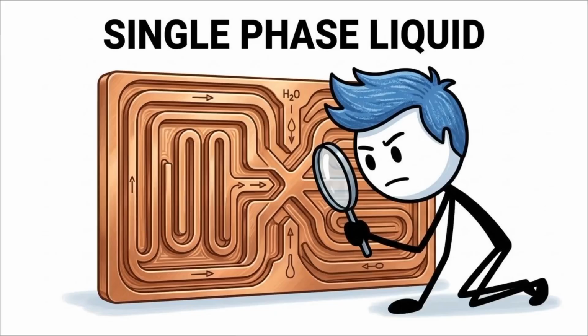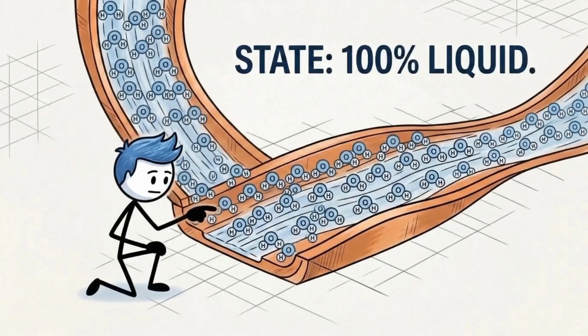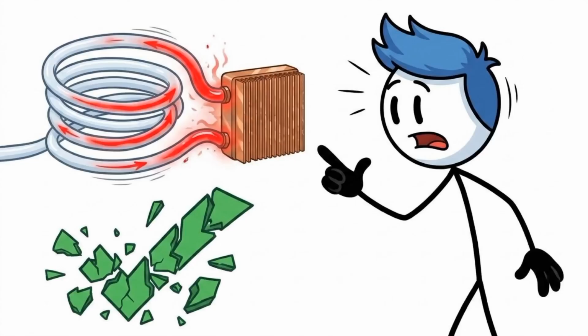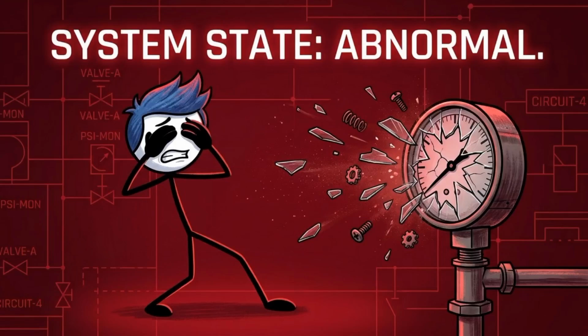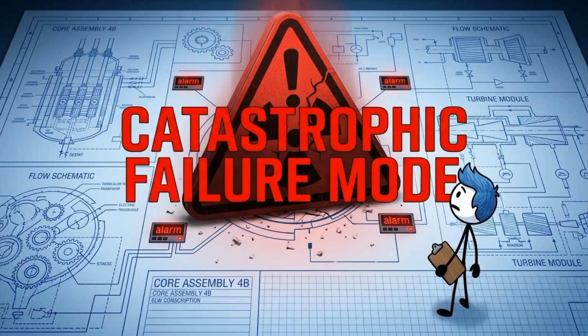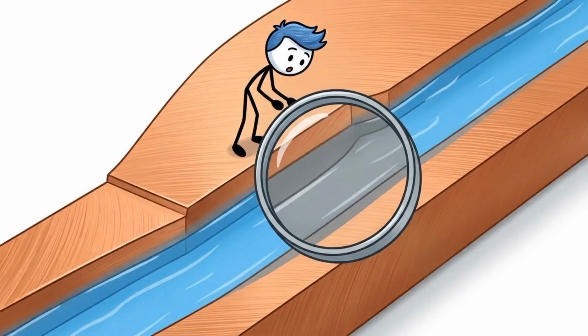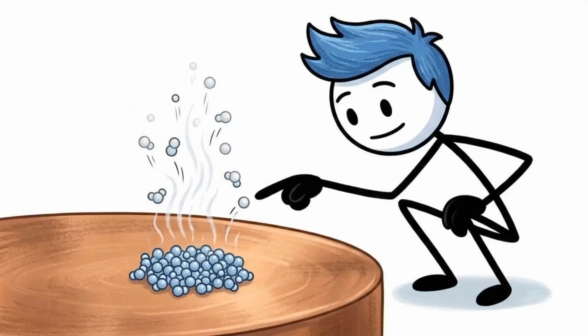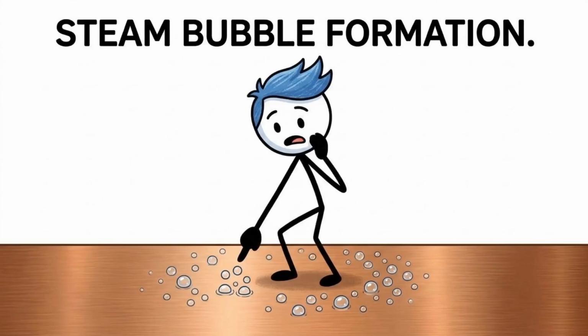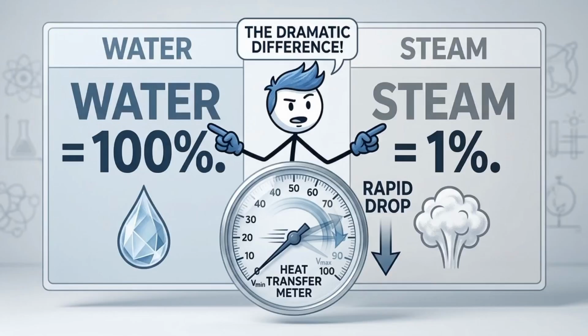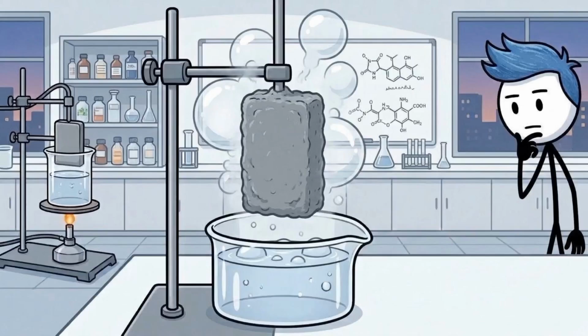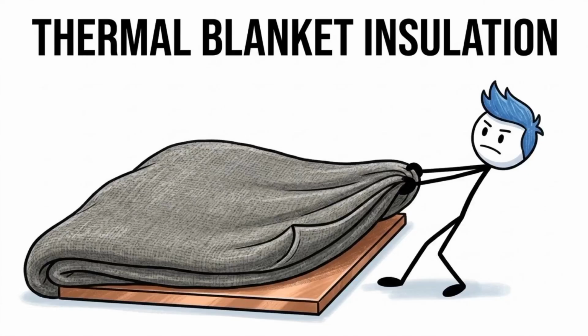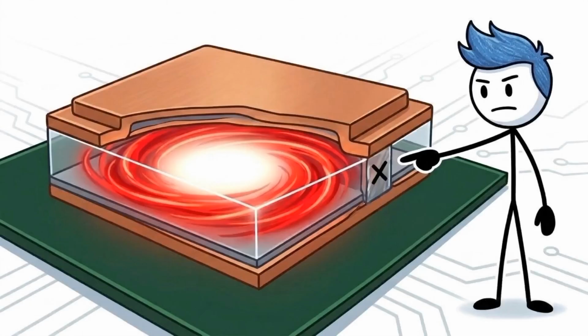Most modern AI data centers rely on single-phase liquid cooling, meaning the fluid is designed to stay strictly liquid. But when the heat backs up past the system's physical limits, it forces an abnormal, catastrophic failure state. The liquid directly touching the microchannels of the copper plate begins to vaporize. Tiny bubbles of steam form on the surface of the copper. Because steam is an incredibly poor conductor of heat compared to liquid water, those micro bubbles act like a thermal blanket. They insulate the chip, trapping the heat inside.